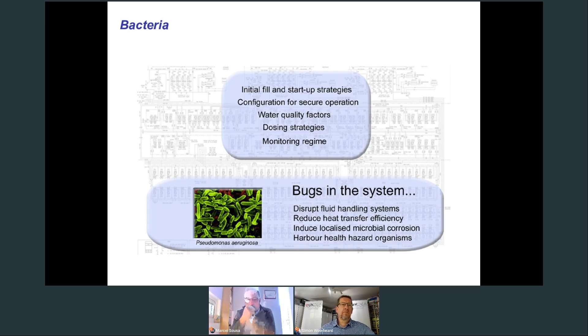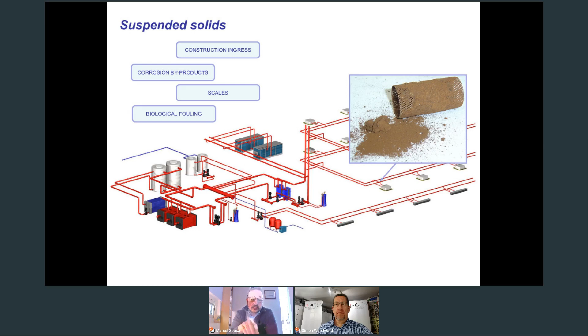Now, suspended solids can be made up of components that are left from the construction phase. It could be corrosion byproducts, scale, and biological fouling. So it's important that high-level filtration is considered. The higher the filtration level, the better the heat transfer efficiencies. And over the last few years, we've seen the introduction in buildings of temperature control systems that have very small apertures. And so even smaller particles can begin to clog up these components, as well as sensors in systems, which then means that those temperature controls are not going to be as effective.